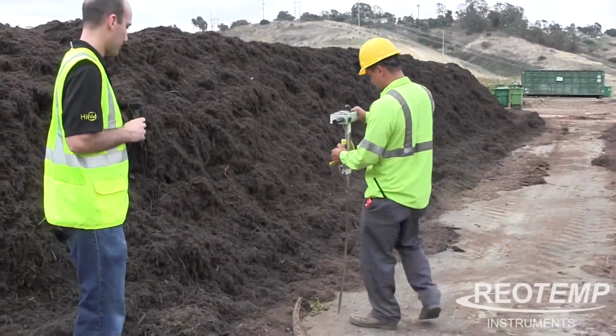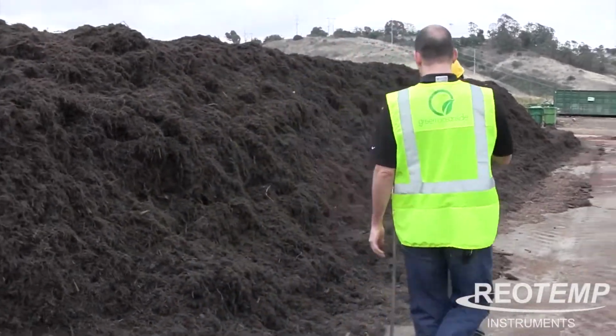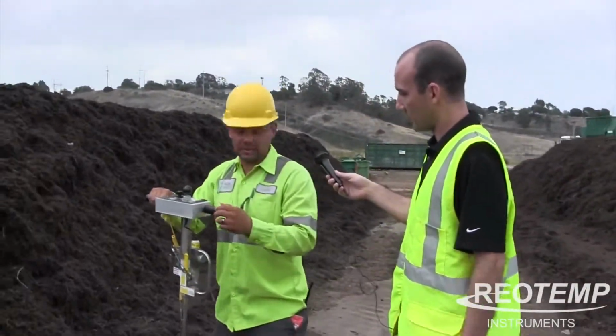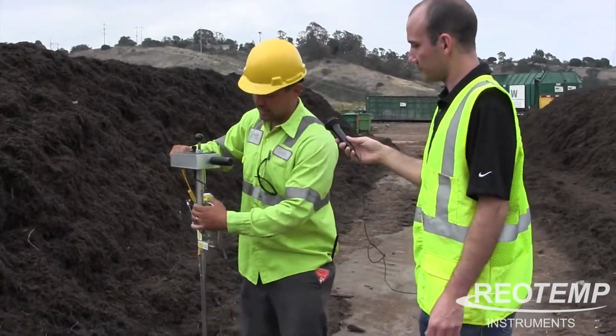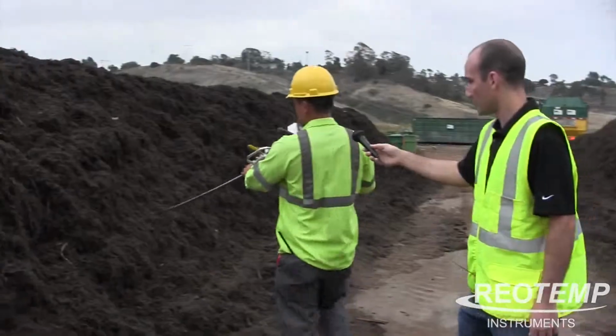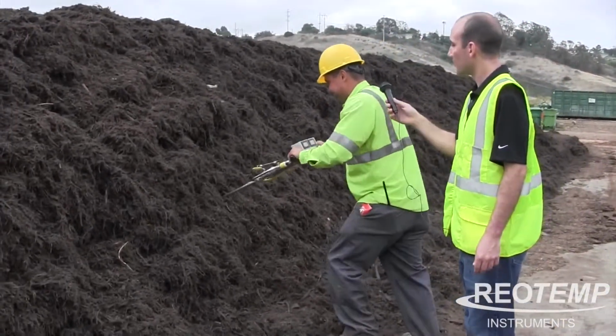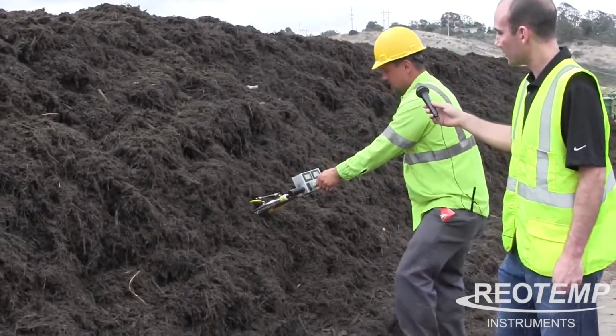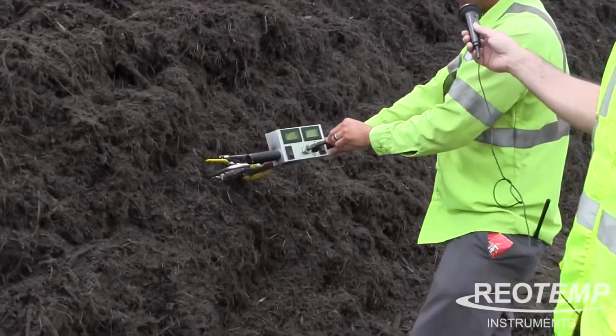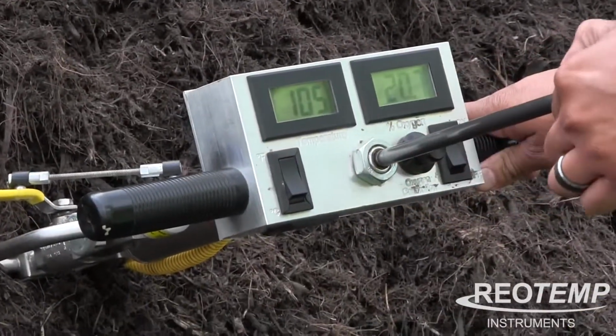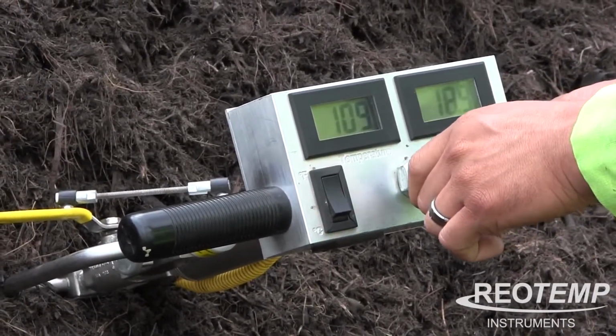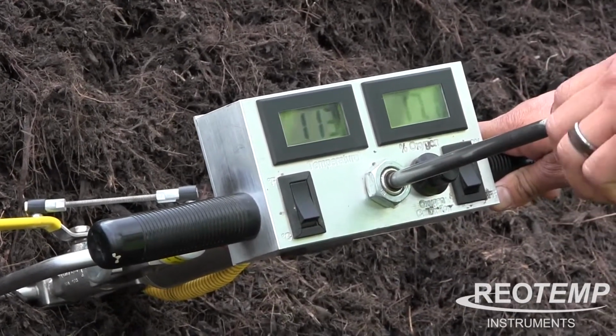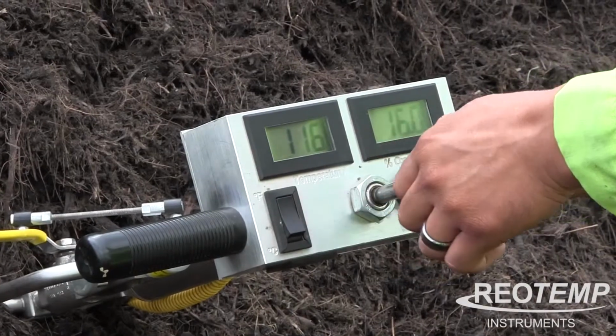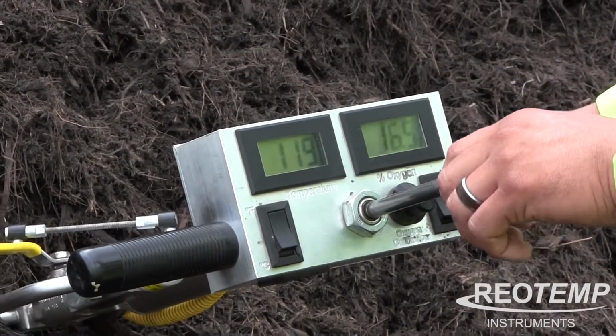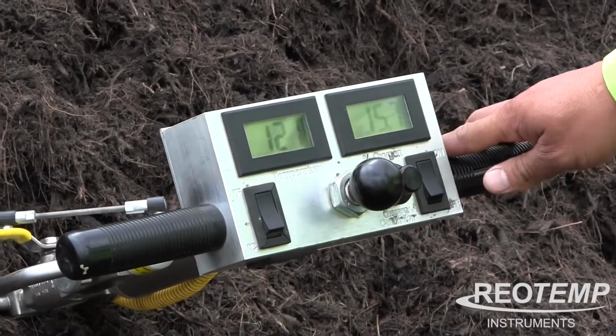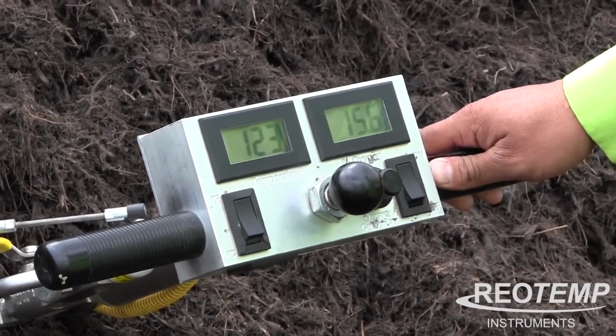Absolutely. Like you said, the first thing I'd normally do is clean the tip out, in case I went to a pile previous to that. I want to clean that out. Once I do that, I can put it back into the sampling position. A bit of pressure. I like to slowly do a couple of pumps just to get that oxygen in there and get the reading. So with the first couple, you're just cleaning out the existing air, and then on the third or fourth one, you're getting a better idea of what the actual reading is going to be. Correct. Okay, so it looks like we're at about 15.6% oxygen.